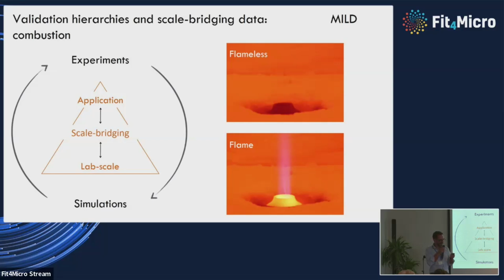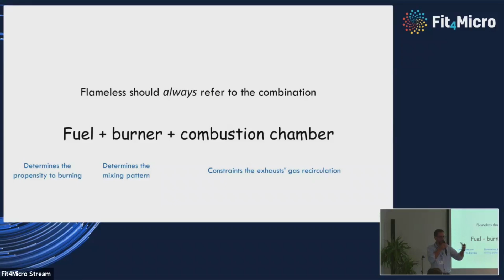The point I want to make is that when we talk about flameless combustion, we should always think about the combination of fuel, burner, and combustion chamber together. Why? Because the fuel properties, as we saw with ammonia and hydrogen, determine the propensity to burning. The burner determines the mixing pattern, and the combustion chamber itself constrains how much you can recirculate inside the burner. It's simple: the larger the volume, the larger the possibility of recirculating exhaust gases.